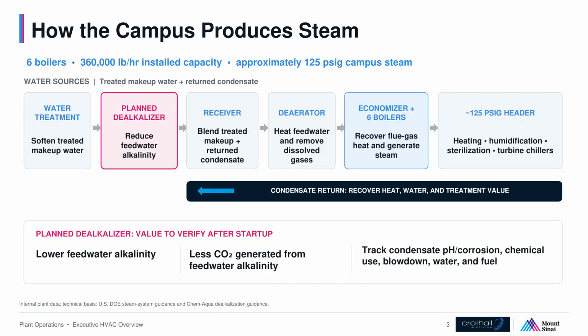Steam begins as a water quality problem. Treated makeup water passes through softeners. The planned dealkalizer sits after those softeners and before the feedwater receiver and deaerator, reducing alkalinity before the water reaches the boilers. Returned condensate joins the treated makeup water in the receiver. The deaerator heats the feedwater and removes dissolved gases. An economizer recovers heat from flue gas, and 6 boilers produce up to 360,000 pounds of steam per hour. The campus header operates at about 125 pounds per square inch gauge. That steam supports heating, humidification, sterilization, and steam turbine chillers.